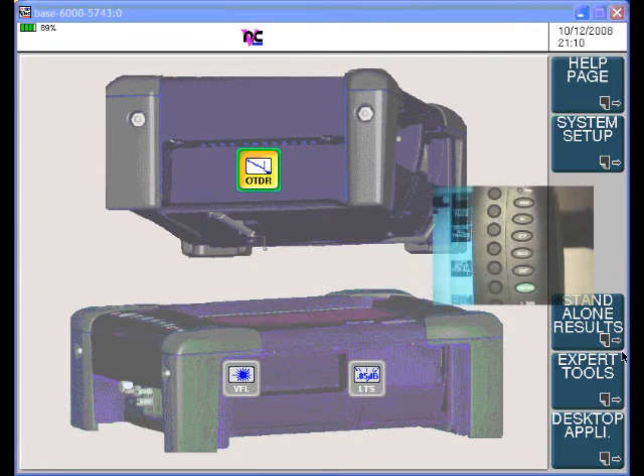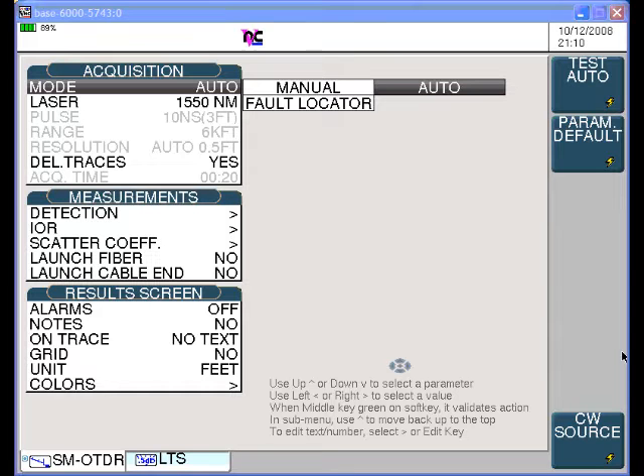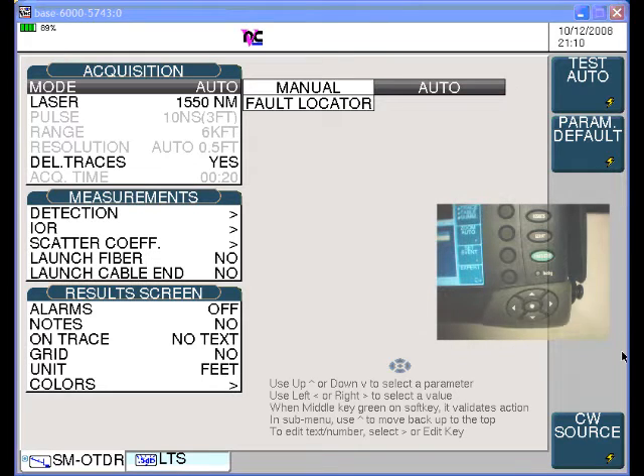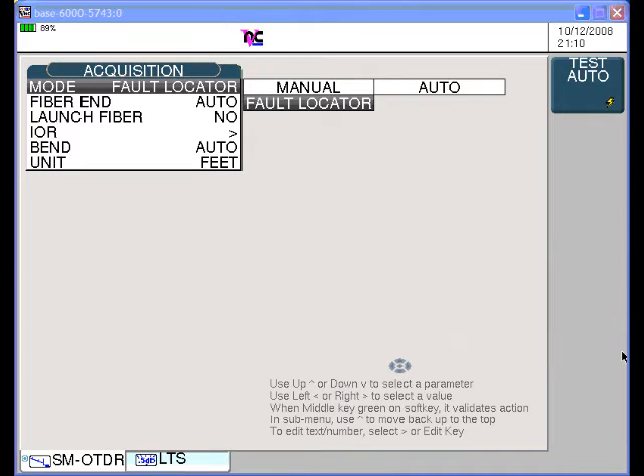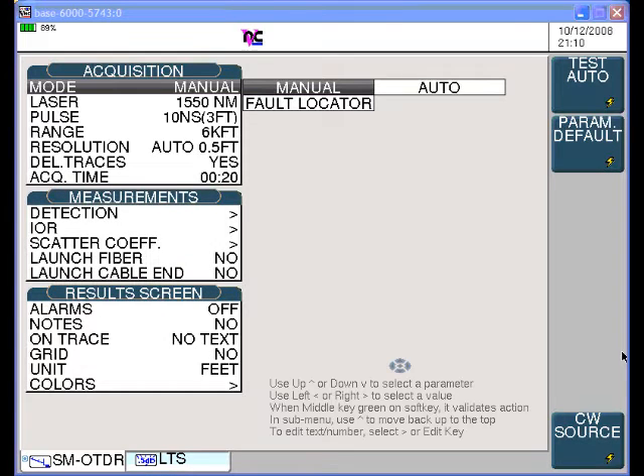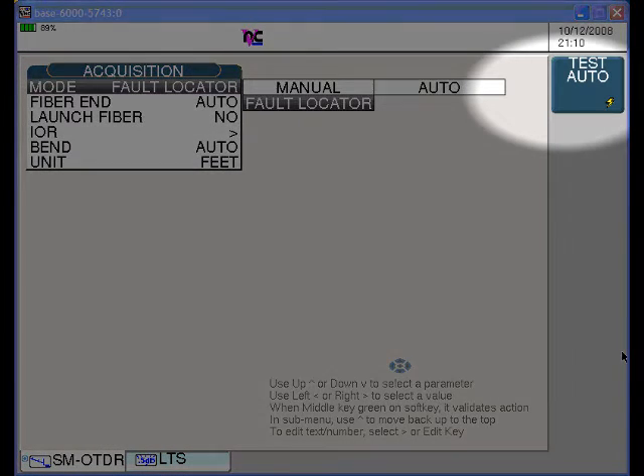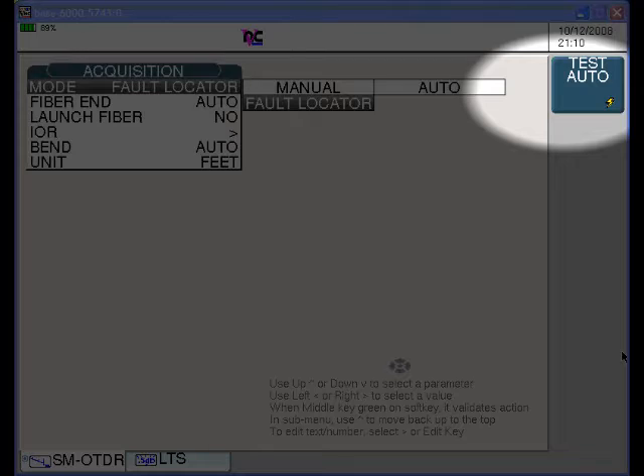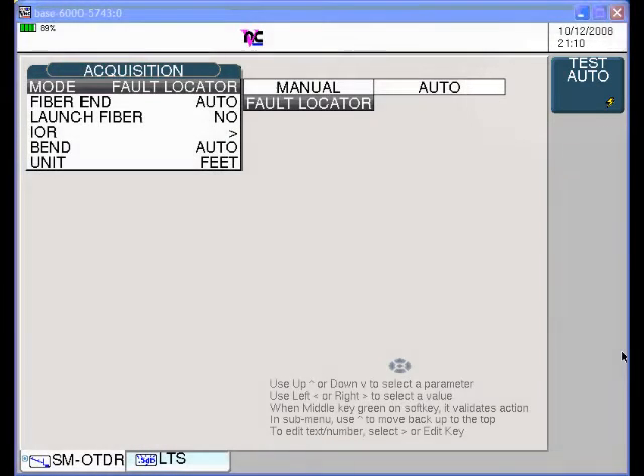Press the setup key and use the arrow keys to select the fault locator function in the mode menu in the acquisition box. The three choices are manual, automatic, or fault locator operation. Then press test auto to set all the fault locator parameters to their defaults. You need not adjust any other fault location parameters.